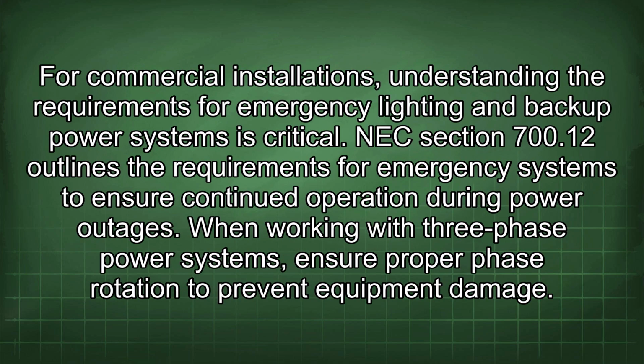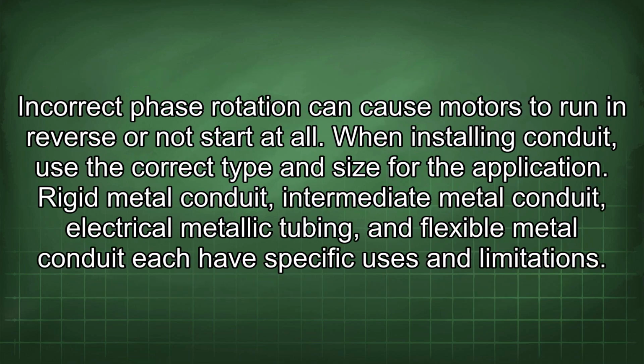For commercial installations, understanding the requirements for emergency lighting and backup power systems is critical. NEC Section 700.12 outlines the requirements for emergency systems to ensure continued operation during power outages. When working with three-phase power systems, ensure proper phase rotation to prevent equipment damage. Incorrect phase rotation can cause motors to run in reverse or not start at all.